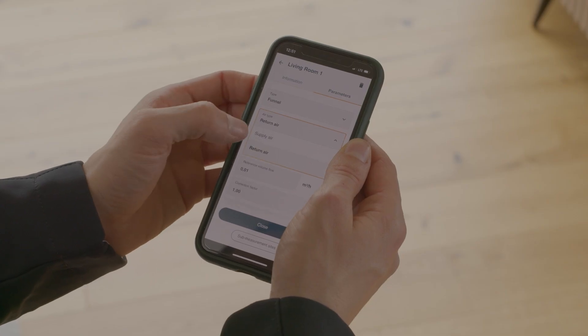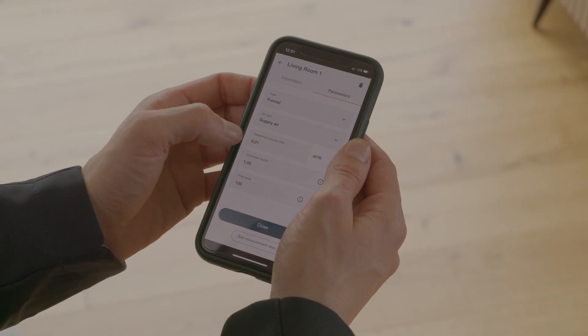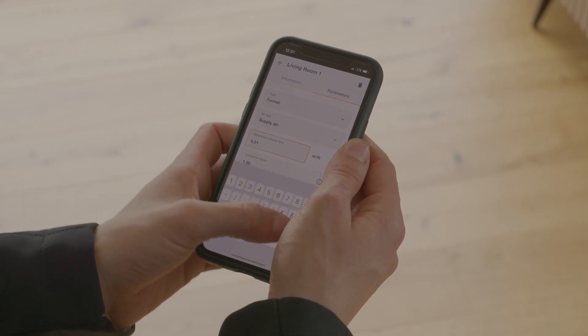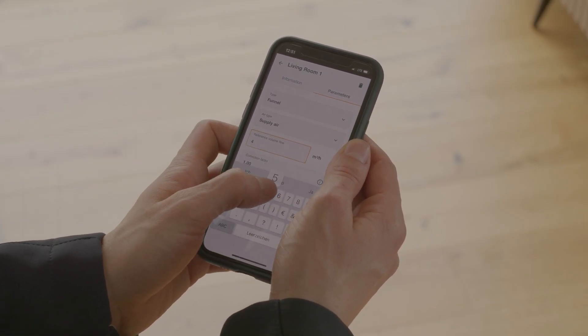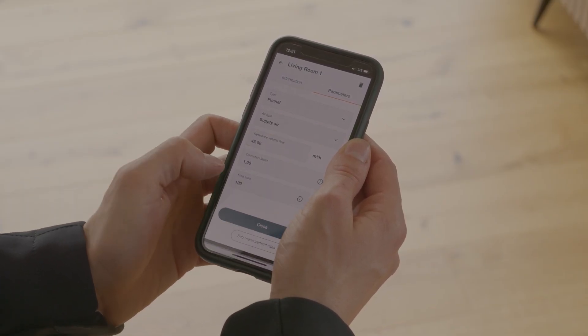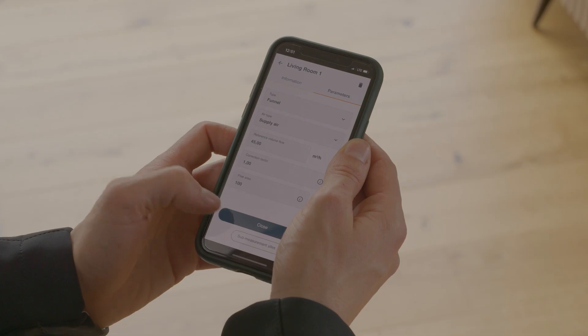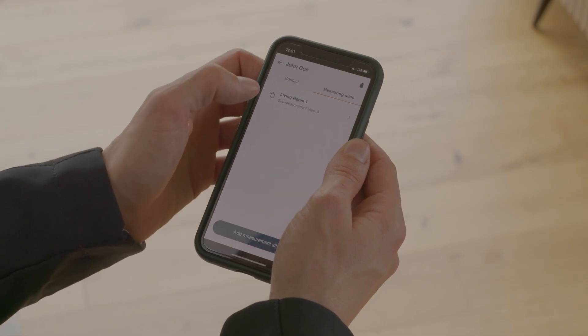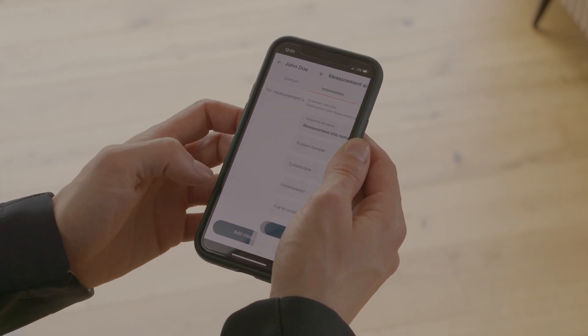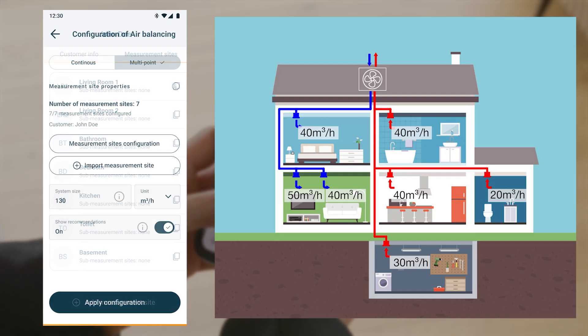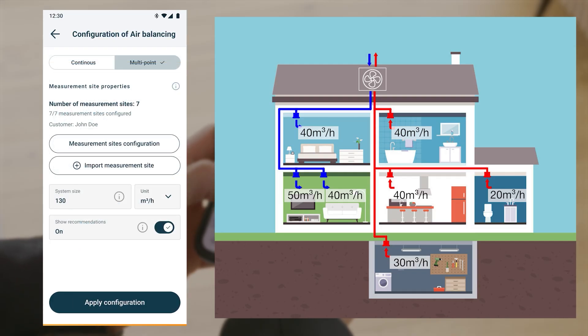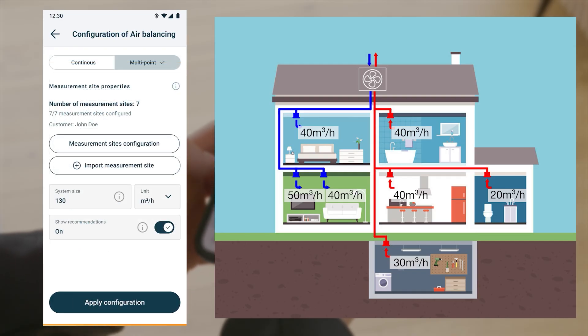Before the measurement, the measuring points must be created in the Testo Smart app and the air type and the reference volume flow must be entered for each measuring point. Once all outlets have been created, the Pro Measuring Program Air Balancing is opened and the measuring points are imported.